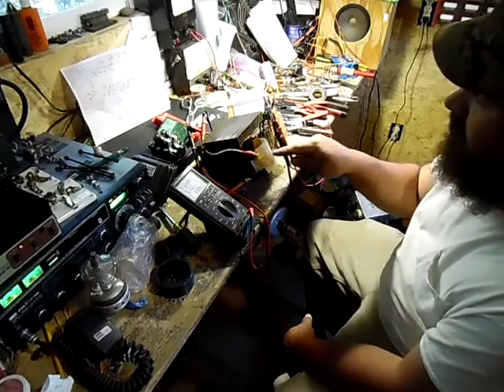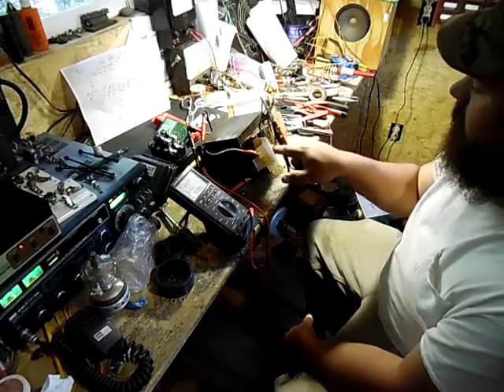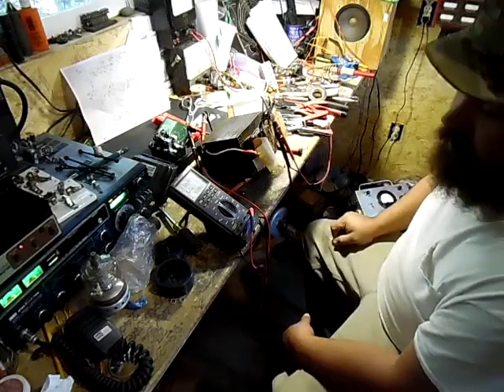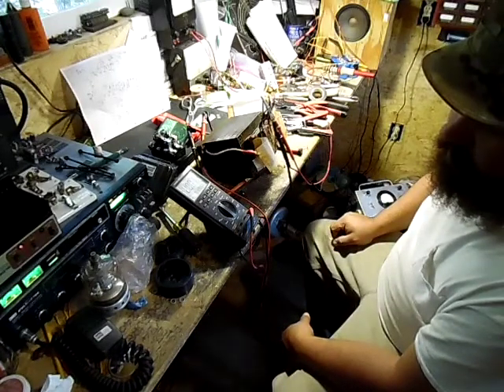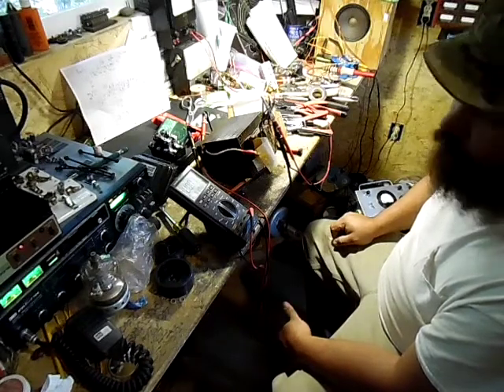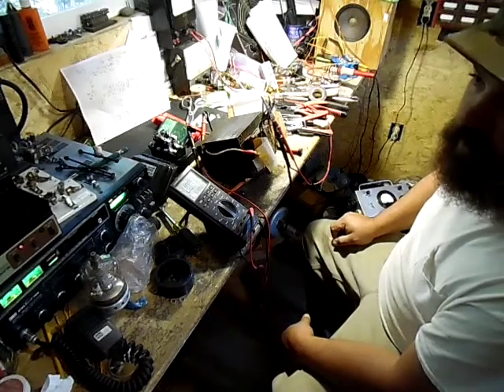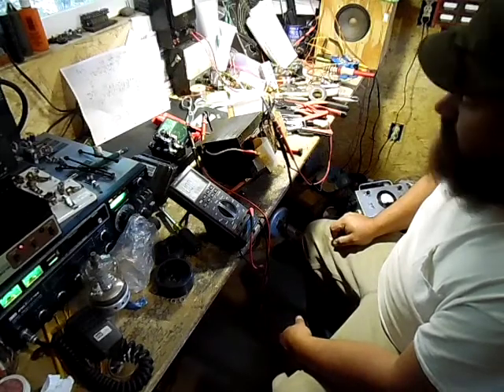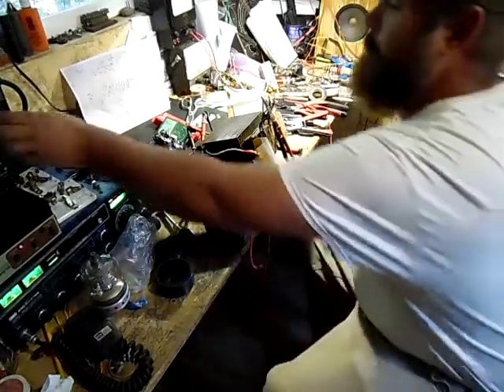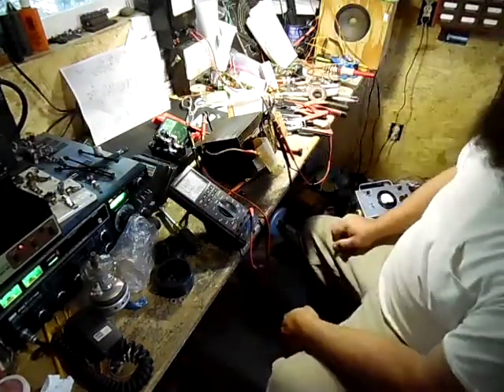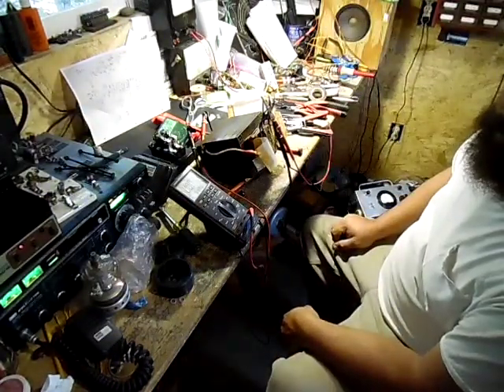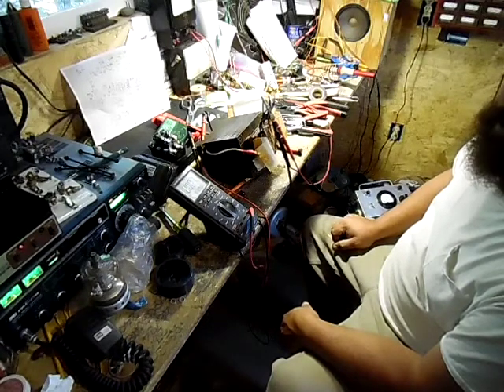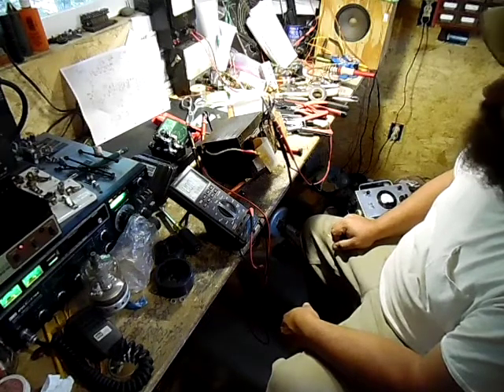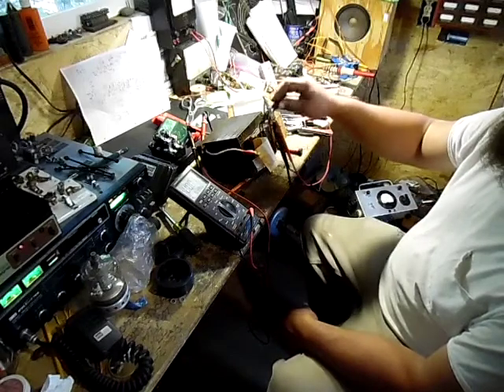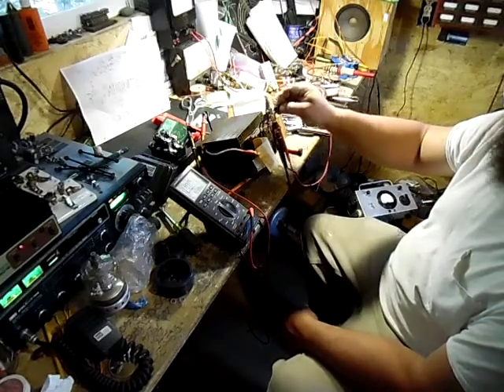When you test this with an ohm meter continuity test, you get like 0.2 ohms. So normally on a primary winding you'd have half an ohm, 0.5 or 0.6. But what I found with this is this winding has like 0.2, 0.1 ohms. It's nearly a dead short, so it's burned up somewhere inside. The other side is a 0.5, which is exactly what it's supposed to be.